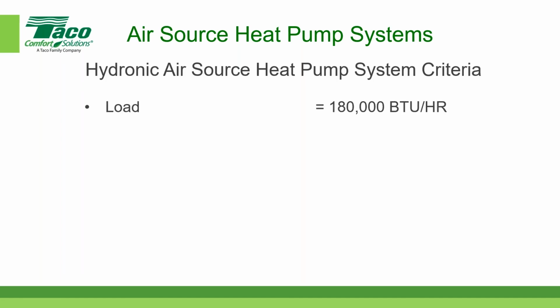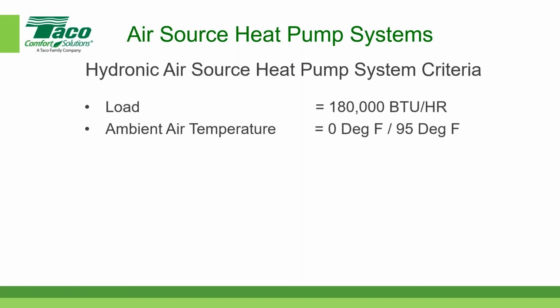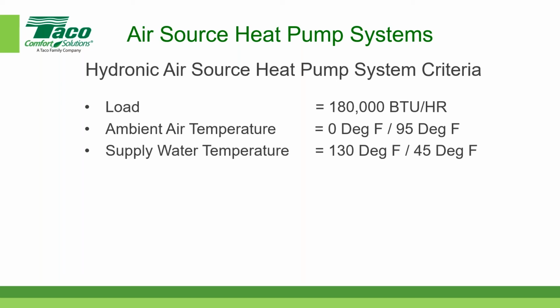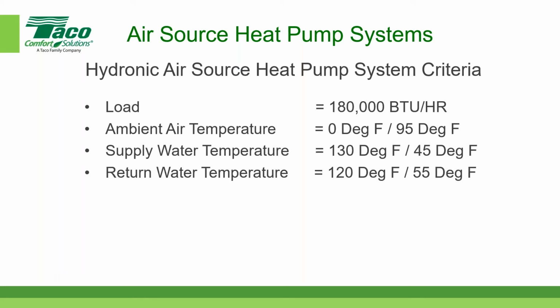So let's design a system. Let's say we had a load of 180,000 BTUs per hour. We had an ambient air temperature of 0 degrees Fahrenheit for winter and 95 degrees Fahrenheit for summer. Supply water temperature of 130 degrees for heating, 45 degrees for cooling. Return water temperature 120 for heating, that's a 10-degree delta T. And a return water temperature for cooling of 55. Notice, this is an important piece here.